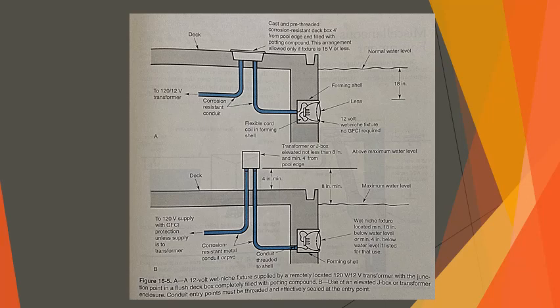This transformer must be located at least 4 feet from the pool edge and elevated 8 inches above the pool deck or ground adjacent to the pool. A flush deck box mounted 4 foot from the pool edge is permitted if the box is fully sealed with potting compound and only if the fixture is rated at 15 volts or less. Figure 16-5 shows many of the main points concerning the wet niche fixtures and various wiring methods.